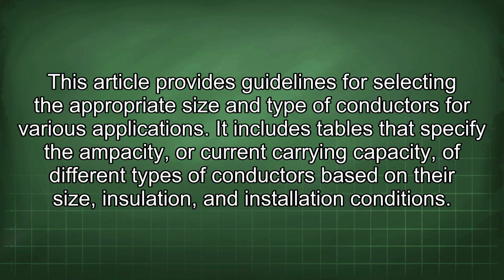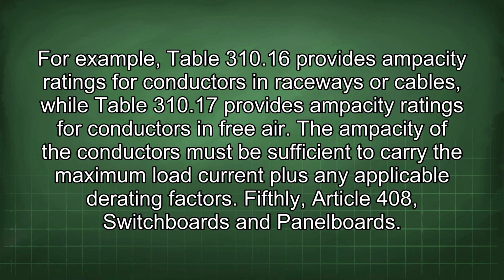It includes tables that specify the ampacity, or current carrying capacity, of different types of conductors based on their size, insulation, and installation conditions. For example, Table 310.16 provides ampacity ratings for conductors in raceways or cables, while Table 310.17 provides ampacity ratings for conductors in free air. The ampacity of the conductors must be sufficient to carry the maximum load current plus any applicable derating factors.